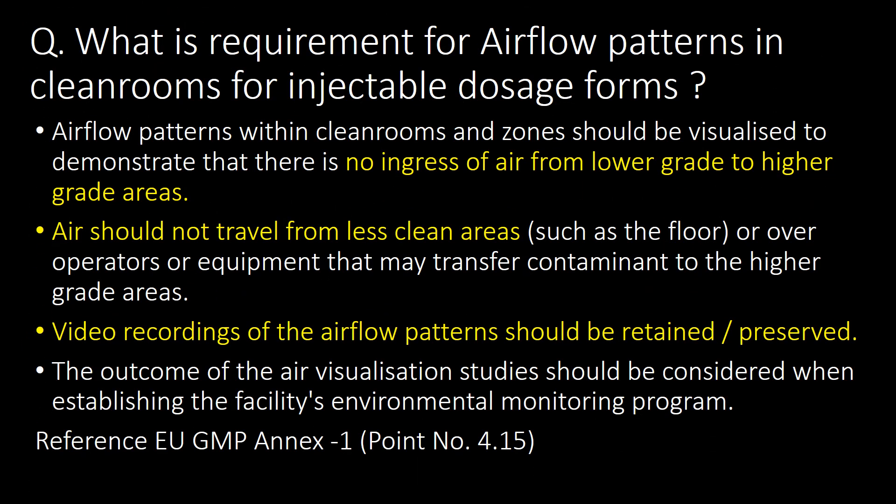What is the requirement for airflow patterns in clean rooms for injectable dosage forms? Airflow patterns within clean rooms and zones should be visualized to demonstrate that there is no ingress of air from lower grade to higher grade areas. Air should not travel from less clean areas or over operators or equipment that may transfer contaminants to higher grade areas. Video recordings of airflow patterns should be retained. The outcome of the air visualization study should be considered when establishing the facility's environmental monitoring program. Reference: EU GMP Annex 1, Point No. 4.15.